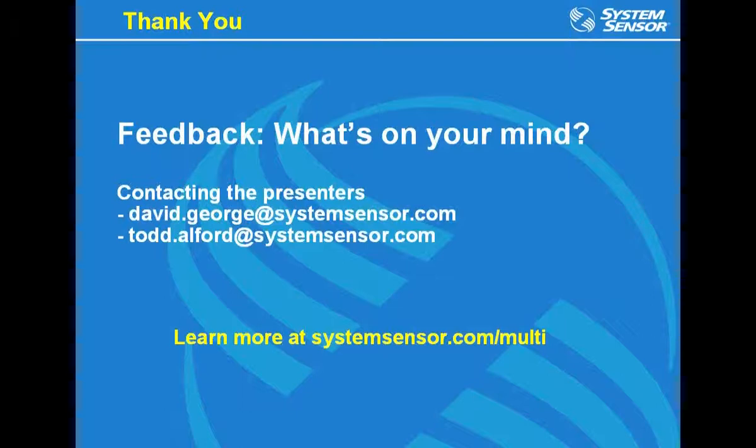Okay. Next question, Todd, is where would you not recommend placing this detector? What types of environments or fire situations? I think the best answer to that is, a lot of people, they first hear about this detector and they think, oh, it's meant to go anywhere. I can use this in any application. And the risk to that is somebody puts this in an extremely dusty, dirty environment. While it would operate in that environment, you're constantly going to be cleaning this device.